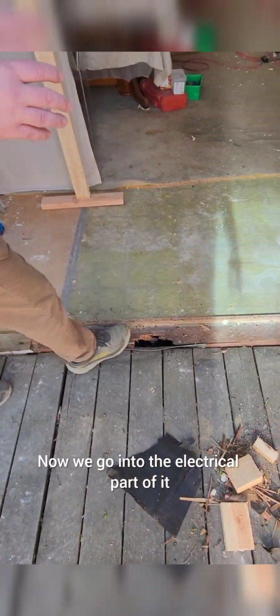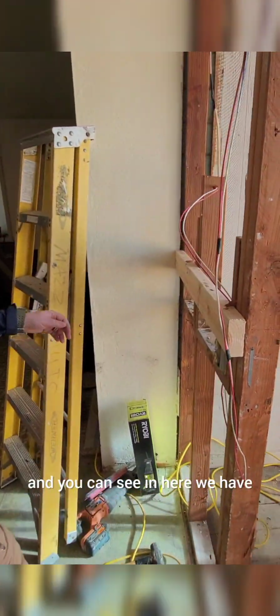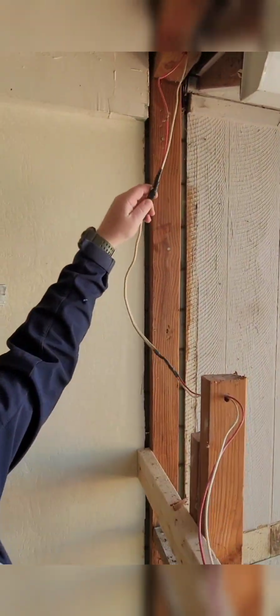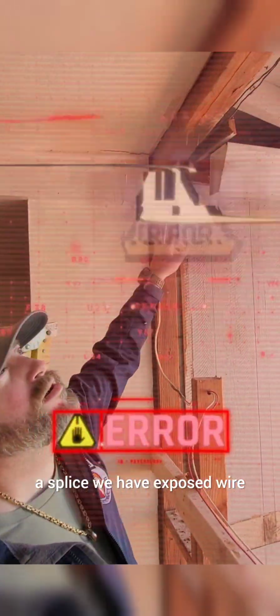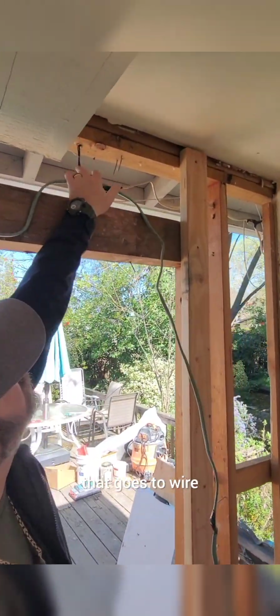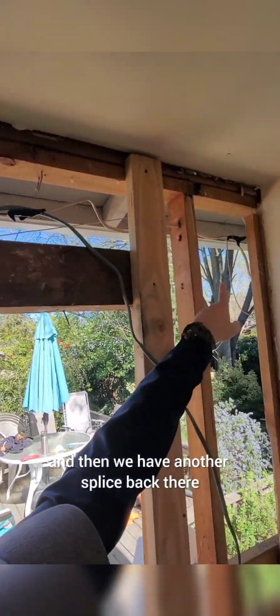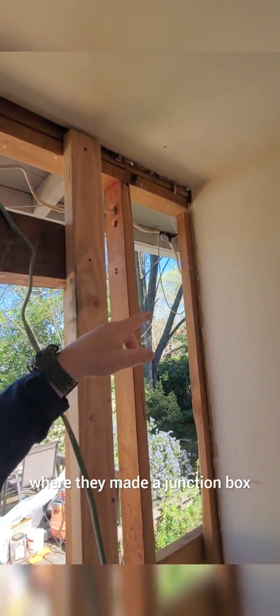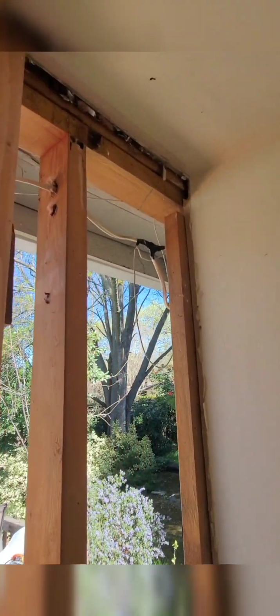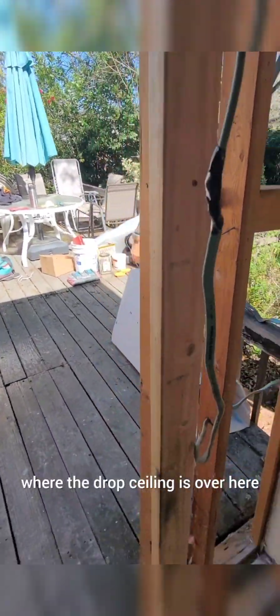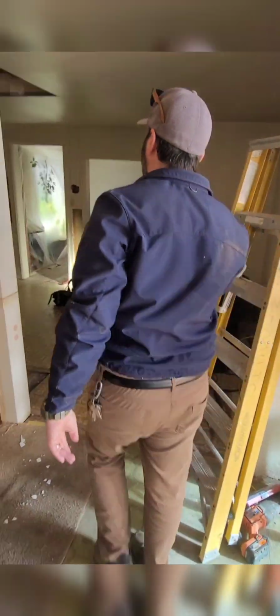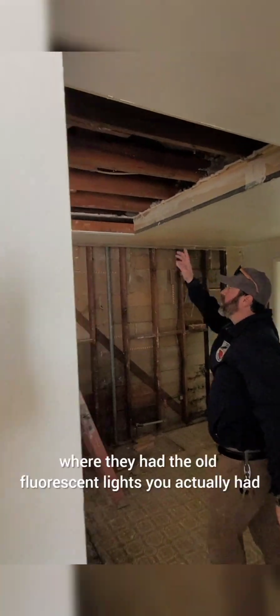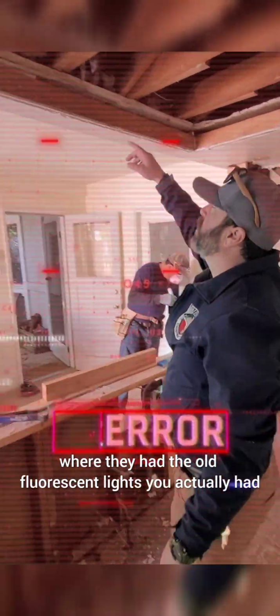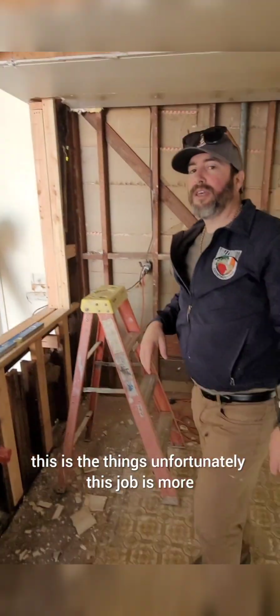Now we go into the electrical part of it, and you can see in here we have a splice. We have exposed wire that goes to another splice that goes through Romex, that goes to another splice that goes to wire, and then we have another splice back there where they made a junction box. And then where the drop ceiling is over here, where they had the old fluorescent lights, you actually had that powered by speaker wire right here.